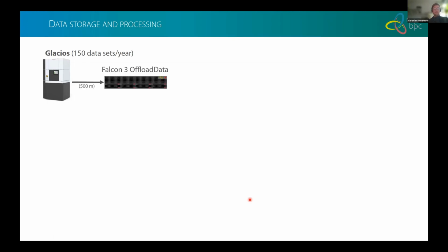The last thing that we optimized, and this was actually the most difficult part, was the data storage and processing. I will only put the Glacios microscope in here, which produces about 150 data sets per year. So every second day, on average, we collect data overnight. Data goes through to the offload data server, which is located 500 meters away from the microscope. This works with multi-mode fiber optics. This is really no problem.